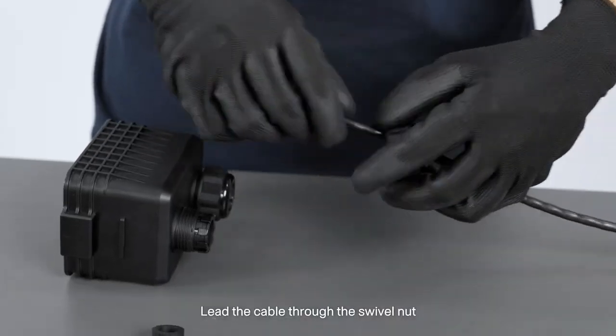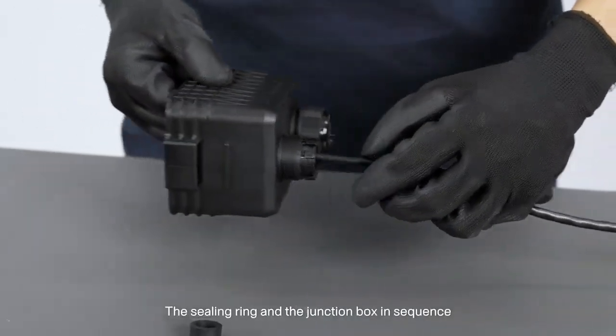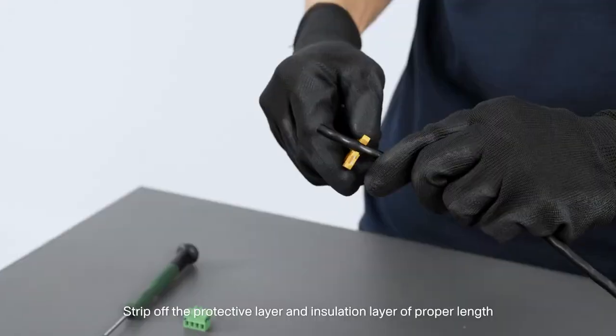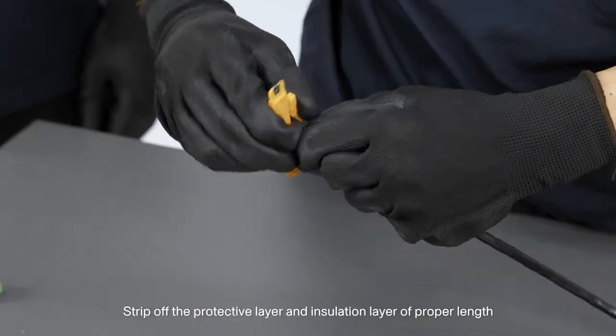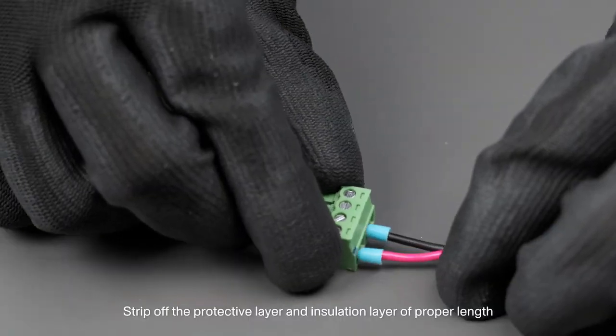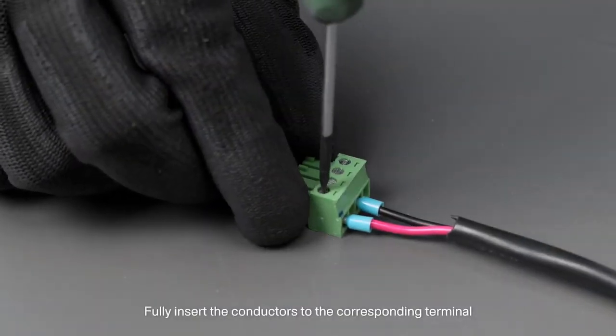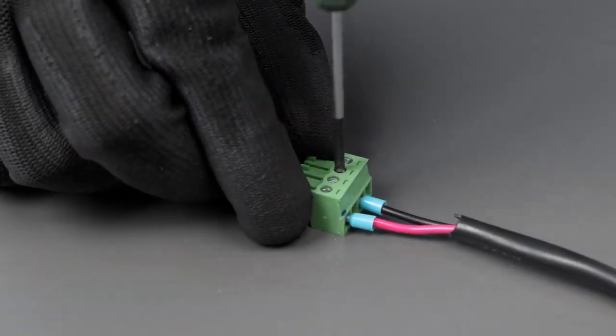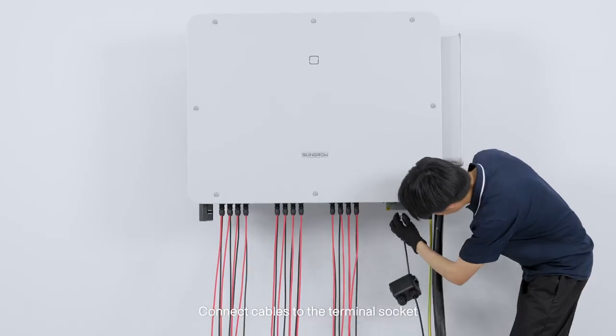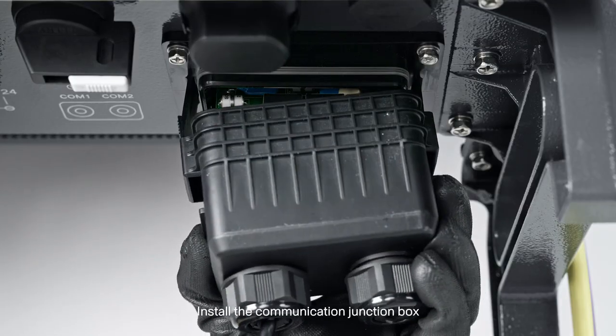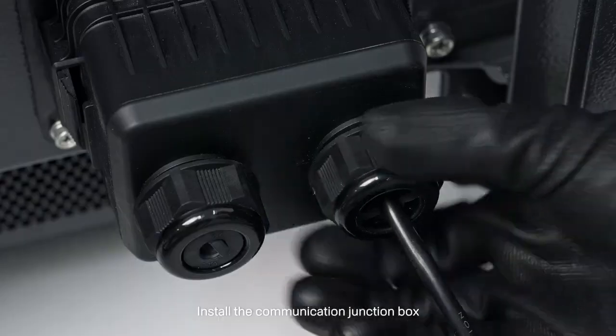Lead the cable through the swivel nut, the sealing ring, and the junction box in sequence. Strip off the protective layer and insulation layer of proper length. Fully insert the conductors to the corresponding terminal. Connect cables to the terminal socket. Install the communication junction box.